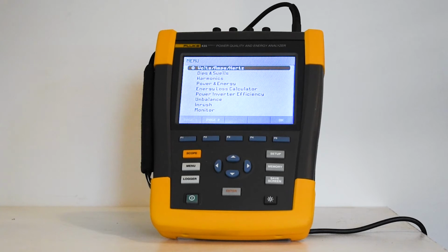Use the up and down and right and left keys to enter the nameplate information. The Motor Analyzer supports motor designs based on NEMA and IEC design types. If the design type is unknown, press Other. In this event, you must consider an additional error of 5% for the mechanical motor parameters.